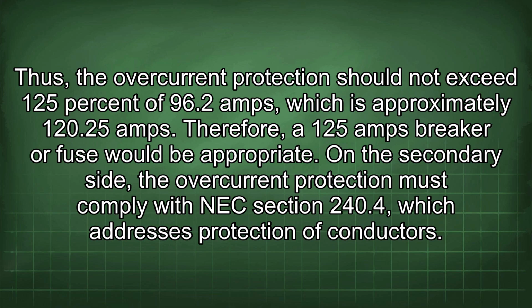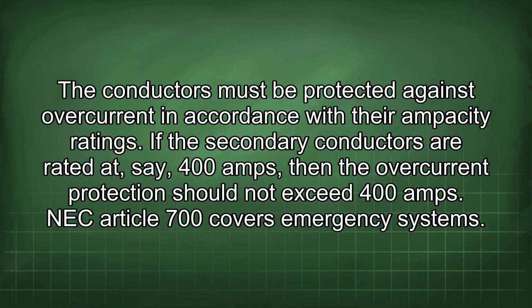On the secondary side, the overcurrent protection must comply with NEC section 240.4, which addresses protection of conductors. The conductors must be protected against overcurrent in accordance with their ampacity ratings. If the secondary conductors are rated at, say, 400 amps, then the overcurrent protection should not exceed 400 amps.